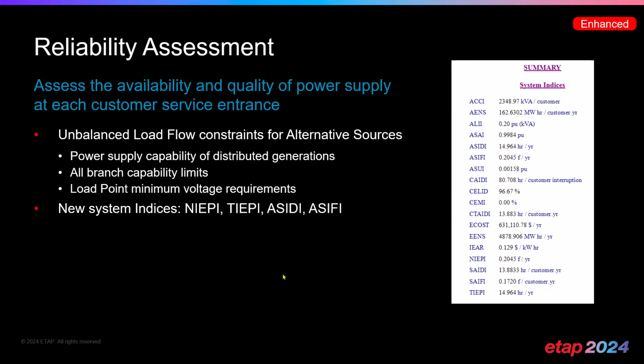We've also enhanced the reliability assessment to include unbalanced load flow. And this unbalanced load flow is a step forward in reliability assessment such that it includes constraints for alternative sources. So as we assess the reliability of the system by looking at multiple sources, we also now look at the constraint based on power flow when we switch to an alternate source, whether we can reliably switch to an alternate source and whether the source can actually supply the power that's needed for the loads that are being switched onto this alternative source, which makes a huge impact to the reliability of the system.